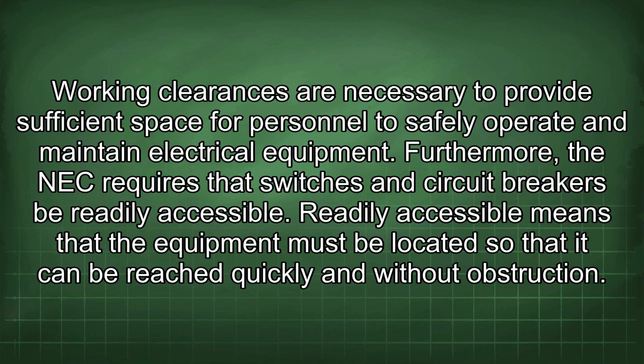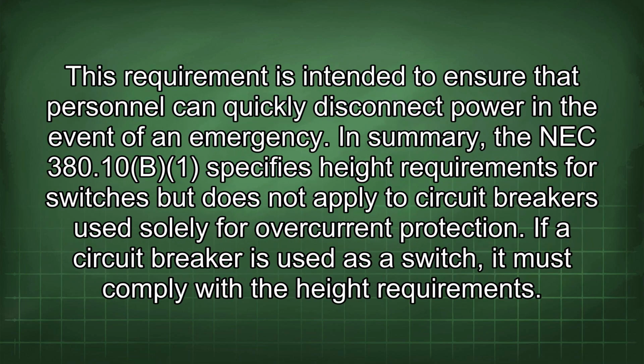Furthermore, the NEC requires that switches and circuit breakers be readily accessible. Readily accessible means that the equipment must be located so that it can be reached quickly and without obstruction. This requirement is intended to ensure that personnel can quickly disconnect power in the event of an emergency.